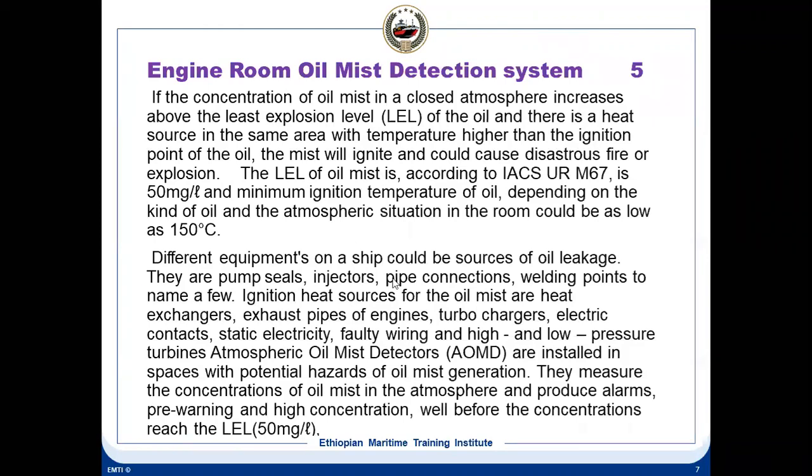Different equipment on the ship could cause oil leakage, as you know. So there are pump seals, injectors, pump connections, welding points. The ignition heat sources for the oil mist are heat exchangers, exhaust pipes, turbochargers, electrical contact, static electricity, faulty wirings. So all these are sources of a spark or ignition source, we can say.